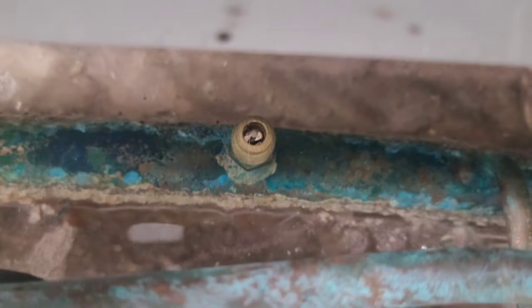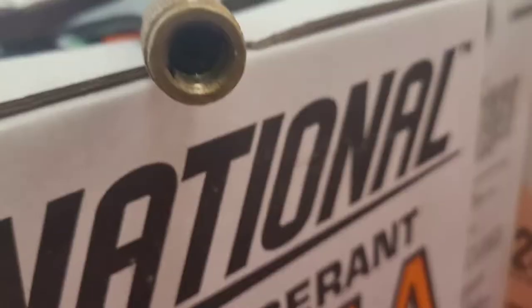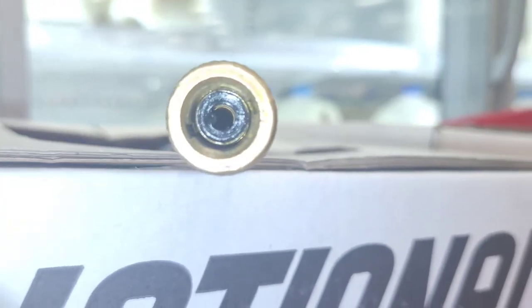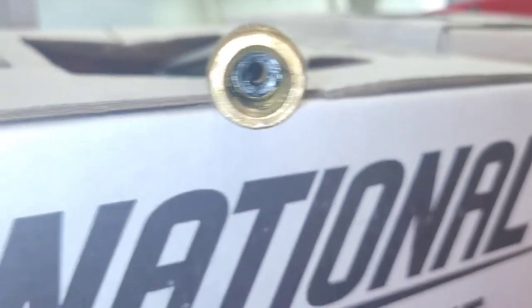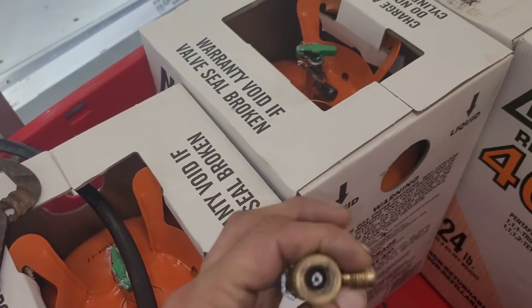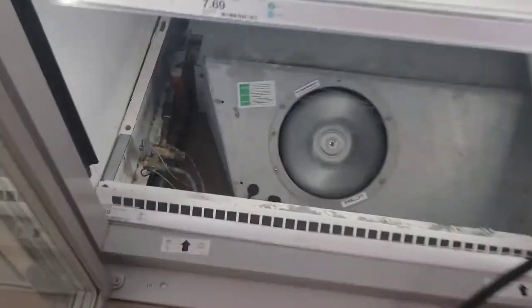How do you do that on a pressurized system? I will show you. So the whole objective is to provide the refrigerant a clear and open quarter inch pathway to flow through. And we do that with this valve stem remover tool. It allows you to remove the valve stem while there's pressure in it.